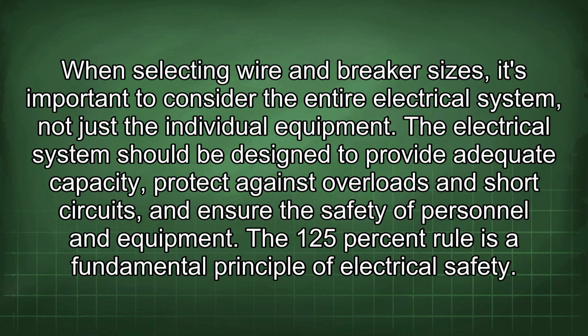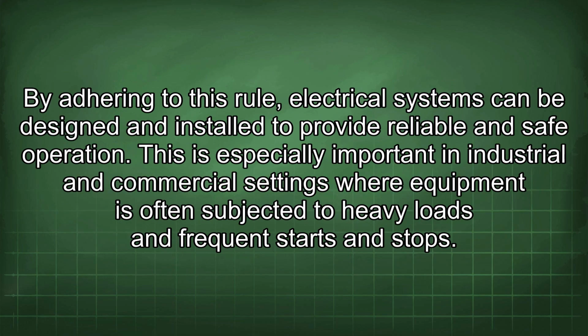When selecting wire and breaker sizes, it's important to consider the entire electrical system, not just the individual equipment. The electrical system should be designed to provide adequate capacity, protect against overloads and short circuits, and ensure the safety of personnel and equipment. The 125% rule is a fundamental principle of electrical safety. By adhering to this rule, electrical systems can be designed and installed to provide reliable and safe operation. This is especially important in industrial and commercial settings where equipment is often subjected to heavy loads and frequent starts and stops.